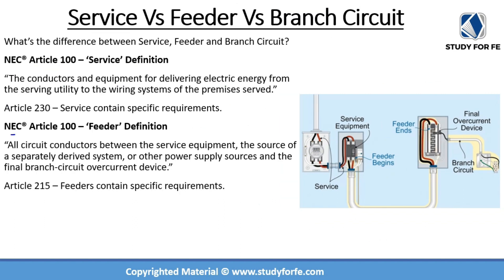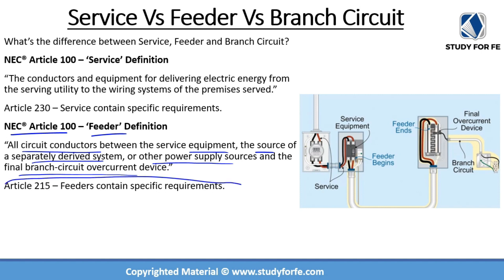What about feeder? Again referring to NEC Article 100, feeders are all circuit conductors between the service equipment, the source of a separately derived system, or other power supply sources, and the final branch circuit overcurrent device. Article 215 contains a lot of relevant and important information about feeders — I highly recommend you go through it, as it is quite commonly used.